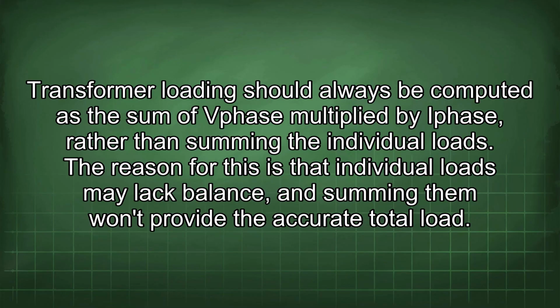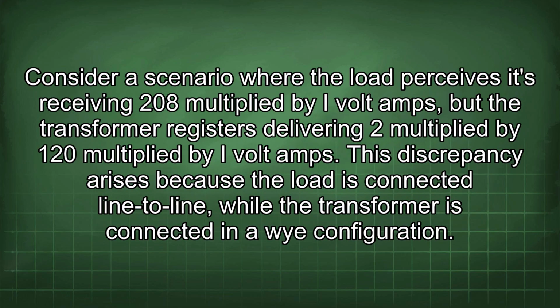Transformer loading should always be computed as the sum of Vphase multiplied by Iphase, rather than summing the individual loads. The reason for this is that individual loads may lack balance, and summing them won't provide the accurate total load. Consider a scenario where the load perceives it's receiving 208 multiplied by I volt amps, but the transformer registers delivering 2 multiplied by 120 multiplied by I volt amps.